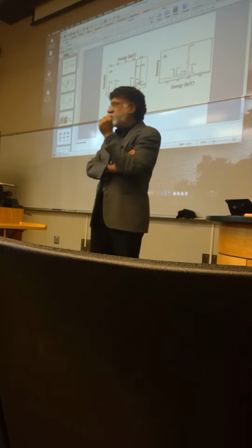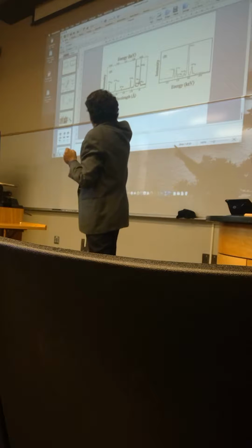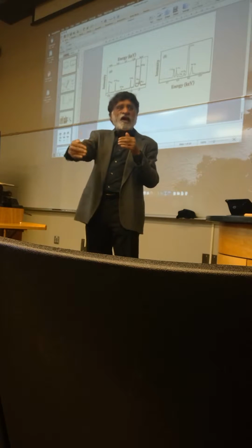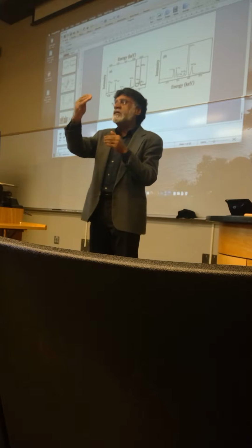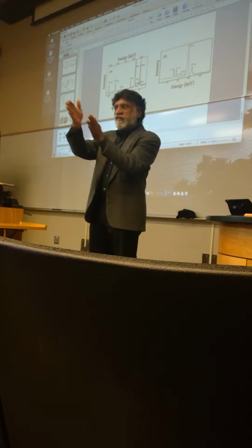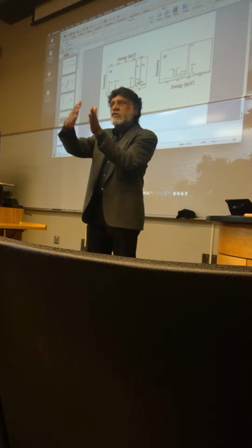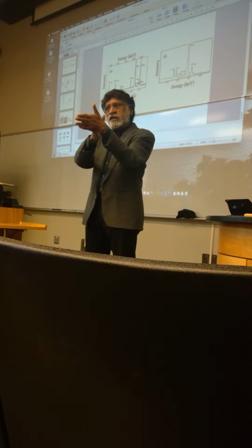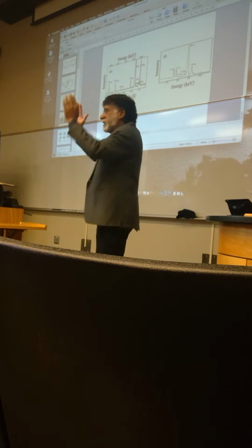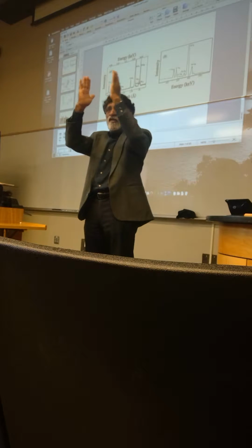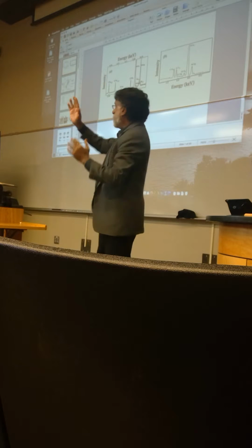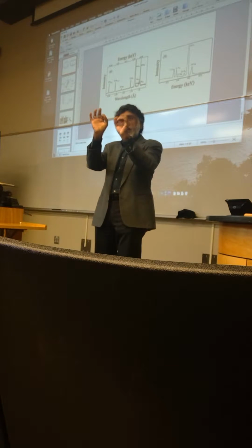The wavelength dispersive detector, which you see here on the left, is sequential. It does one wavelength after the other. It sets up the diffraction condition for that particular wavelength. It has a crystal, it sets up the diffraction condition, and then it scans over different wavelengths by rotating the diffracting crystal. As a result, you can see that the peak widths are very narrow.